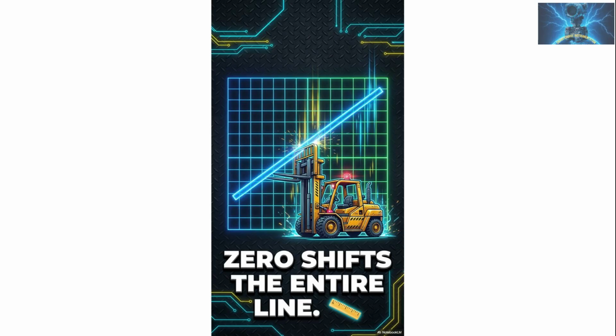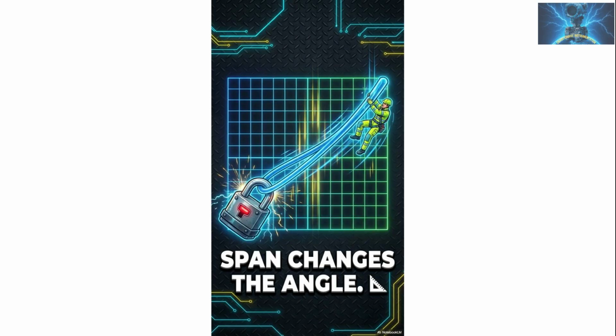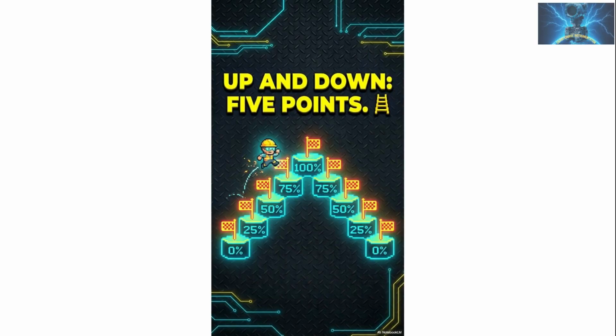If the whole line shifts up or down together, that is zero error. Same slope, wrong starting point. If the angle changes, that is span error. The low end may look fine, while the high end is lying straight to your face. Test it going up and test it coming down. Hit 5 points: 0, 25, 50, 75, and 100%. Not just 0 and span and a prayer.